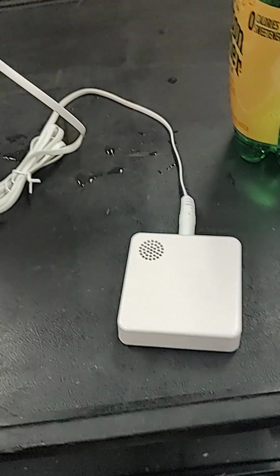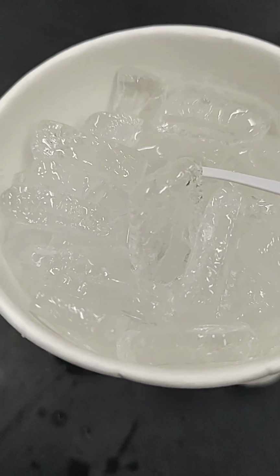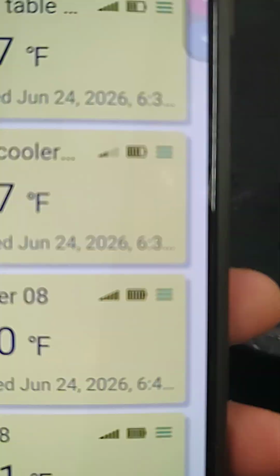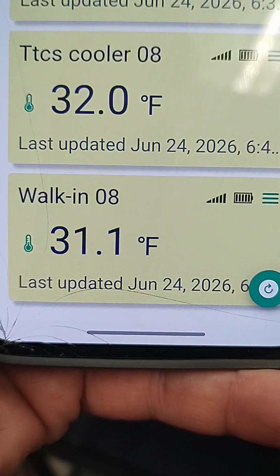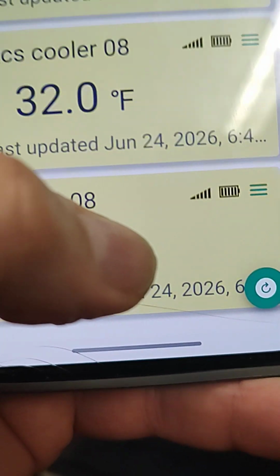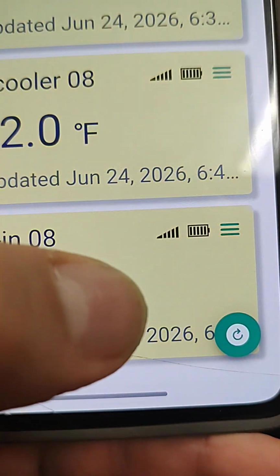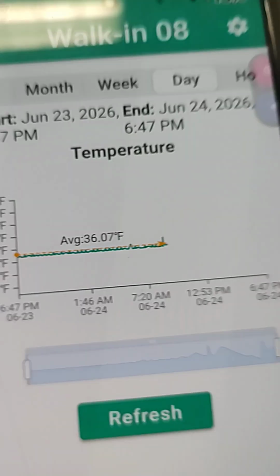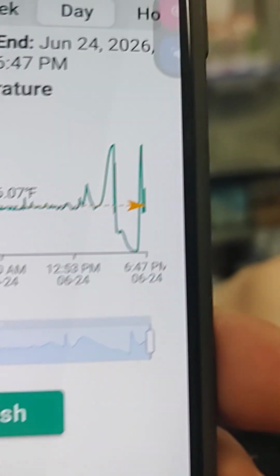Okay, first things first, we're going to ice point this sensor. It's been relaxing in its ice bath for a little while. We go look at the main screen. It says it's pulling 31.1 degrees, which is 0.9 degrees below the correct ice point.